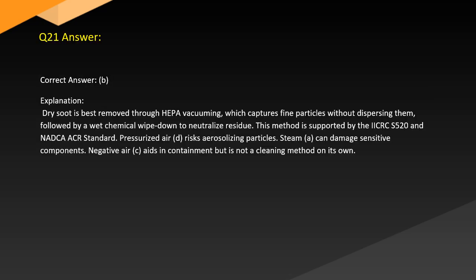Answer. Correct answer: B. Explanation. Dry soot is best removed through HEPA vacuuming, which captures fine particles without dispersing them, followed by a wet chemical wipe down to neutralize residue. This method is supported by the IICRC S520 and NADCA ACR Standard. Pressurized air, D, risks aerosolizing particles. Steam, A, can damage sensitive components. Negative air, C, aids in containment but is not a cleaning method on its own.